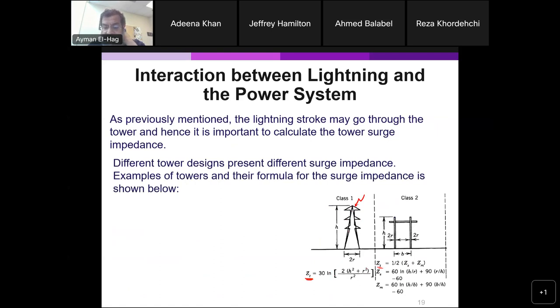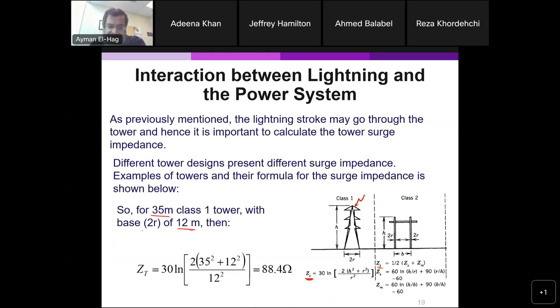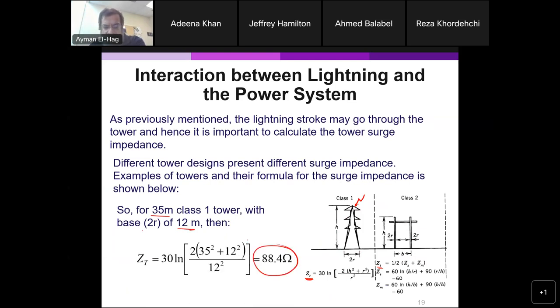For example, here this is equal to 2 times h squared plus r squared. H is the length, r is the width at the ground level. This is a lattice structure. This is basically a wooden pole, okay, and here are all the dimensions. So each design, based on its dimensions, will have a certain surge impedance. For example, for this design, if you have a 35 meter class one, which is this one, with base equal to 12 meter, very straightforward, your surge impedance becomes equal to 88.4.